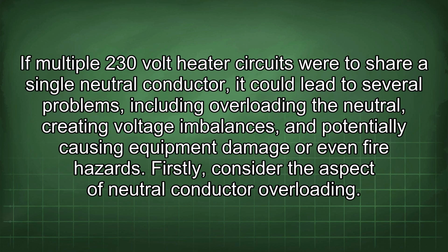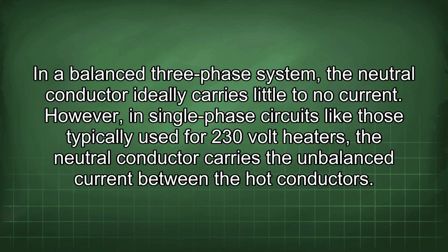If multiple 230-volt heater circuits were to share a single neutral conductor, it could lead to several problems, including overloading the neutral, creating voltage imbalances, and potentially causing equipment damage or even fire hazards. Firstly, consider the aspect of neutral conductor overloading. In a balanced three-phase system, the neutral conductor ideally carries little to no current.